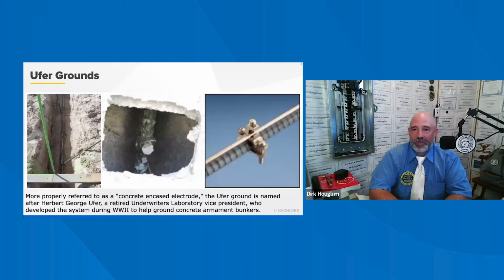With so many homes and commercial buildings now built on concrete slabs, the Ufer grounding system has become very common. The requirements for Ufer grounds are that they have either 20 feet of number 4 rebar or number 4 AWG copper wire embedded in at least 2 inches of solid concrete within the footer that is in contact with the earth. This system must also have an external means of connecting another ground system to it, like for your telephone lines or something to that effect.